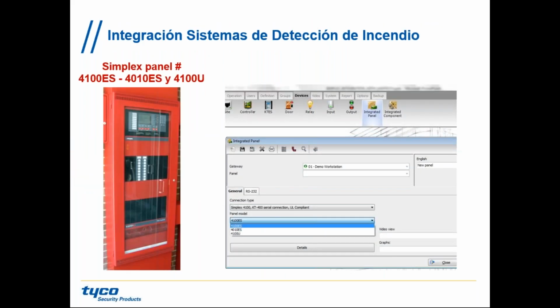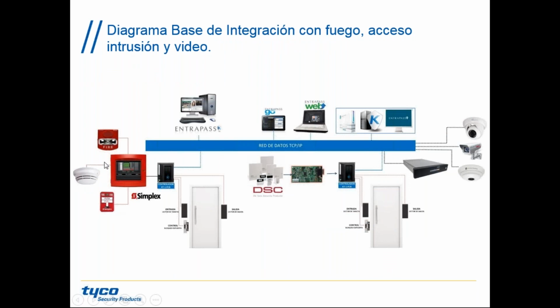Fire alarm integration: the Simplex panel. Now we add the Simplex panel to the KT1, and the KT1 to the network. The software will read all the outputs and inputs of the Simplex system, but it won't control the system because that's against the standard—you cannot configure or control a fire alarm remotely. It is not allowed by the standard.